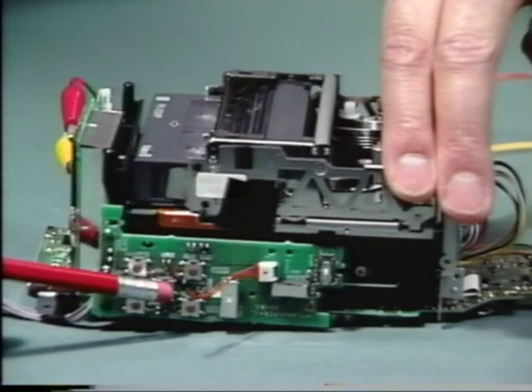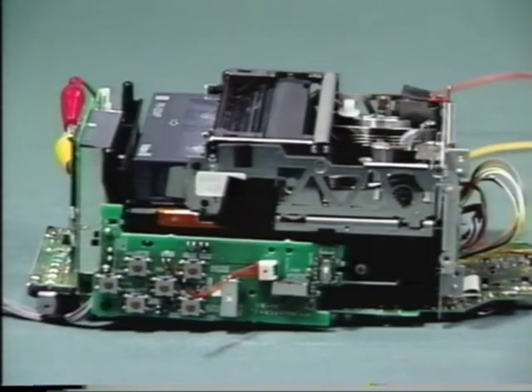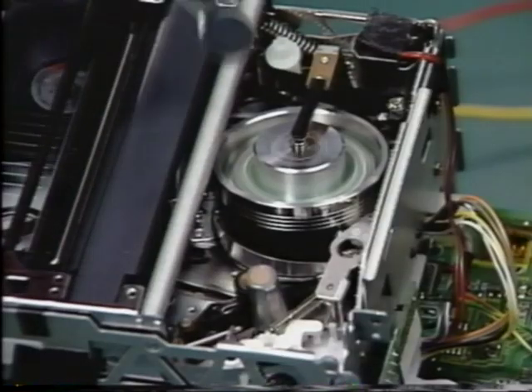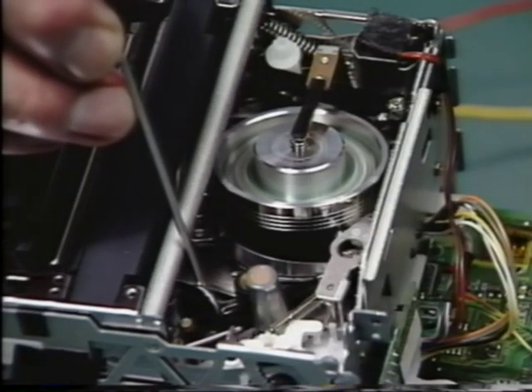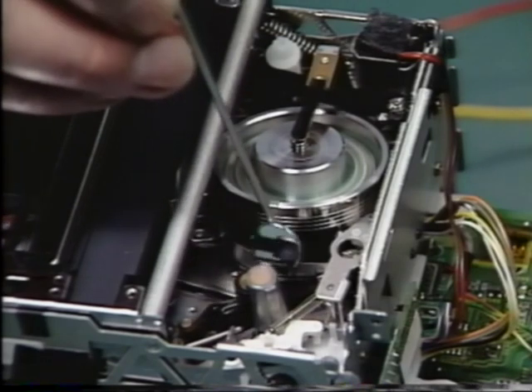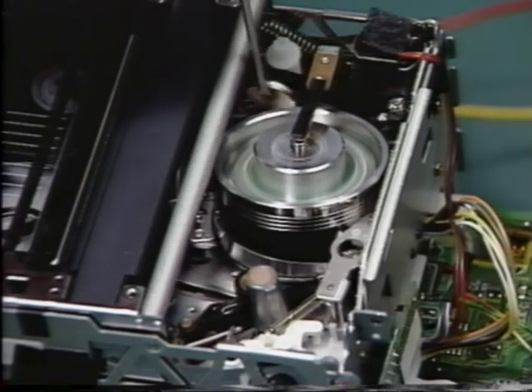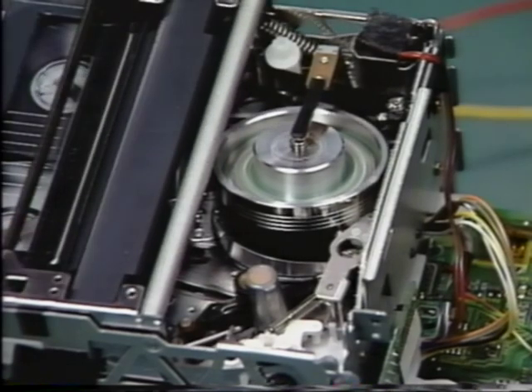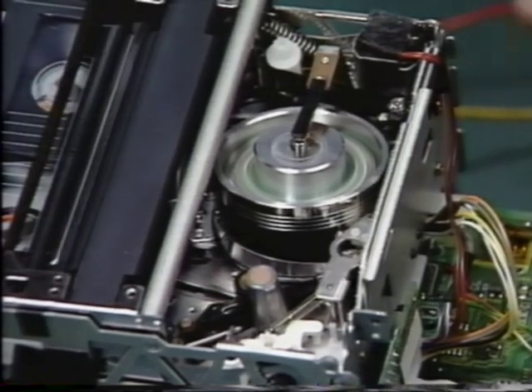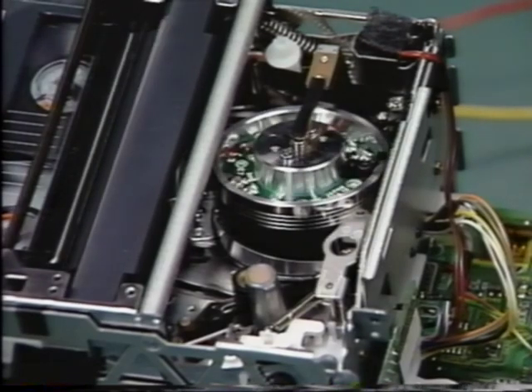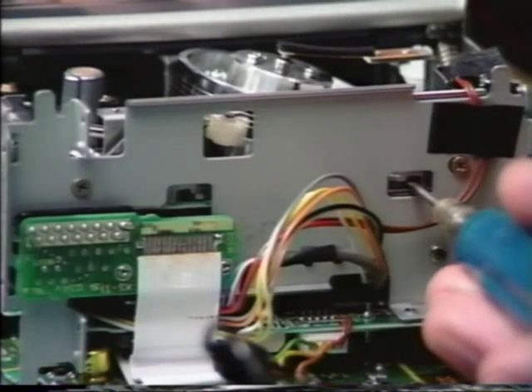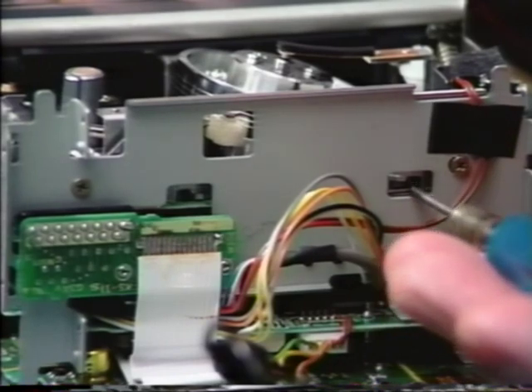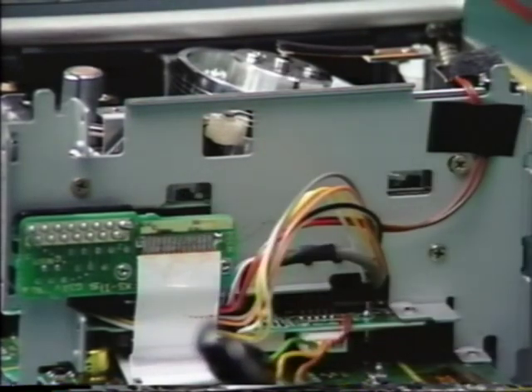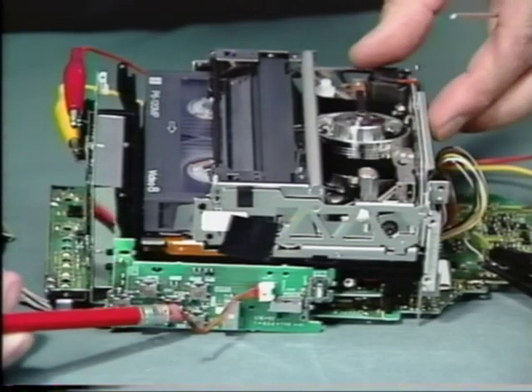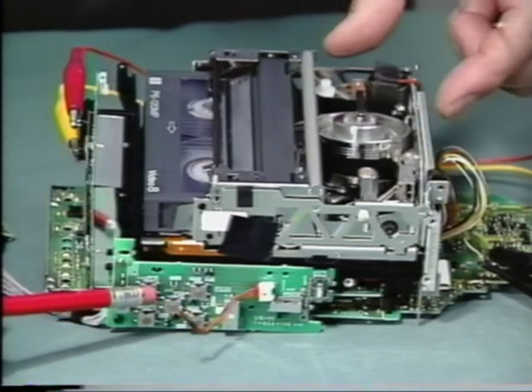Press play. Again, inspect the tape guides with a dental mirror for tape float or curl. If no float or curl is observed, press stop. Tighten the number 3 and number 6 tape guide post lockdown screws. Press play and then rewind to execute the review mode.